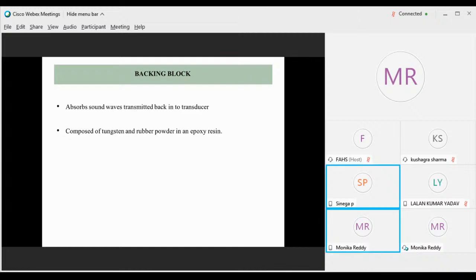So backing block. The backing block is where the transmitted echoes will not escape. It absorbs the sound waves which are transmitted back to the transducer. When the echo pulses don't reach the tissue and are reversing back, the backing block will absorb all the sound. If the backing block is cracked, these sound waves will cause image artifacts. They will revert back to the tissue, and again back to the crystal, so it doesn't produce a proper image. So the backing block is required to absorb the sound waves which are not transmitted into the tissue and would go back to the transducer. It is composed of tungsten and rubber powder in an epoxy resin.